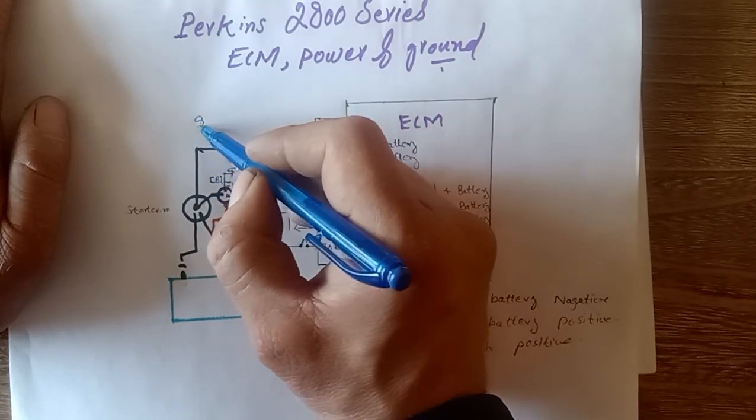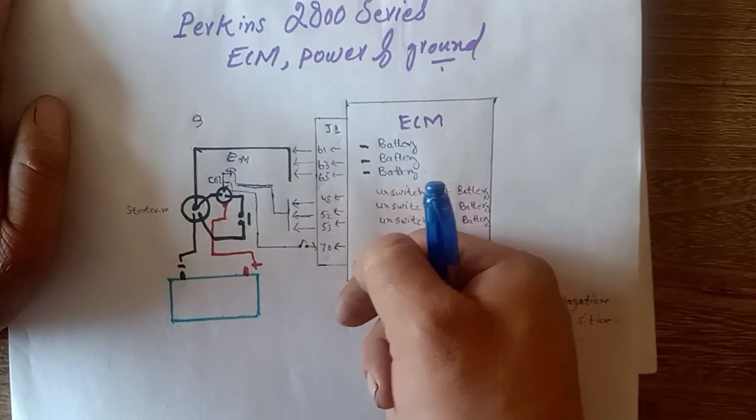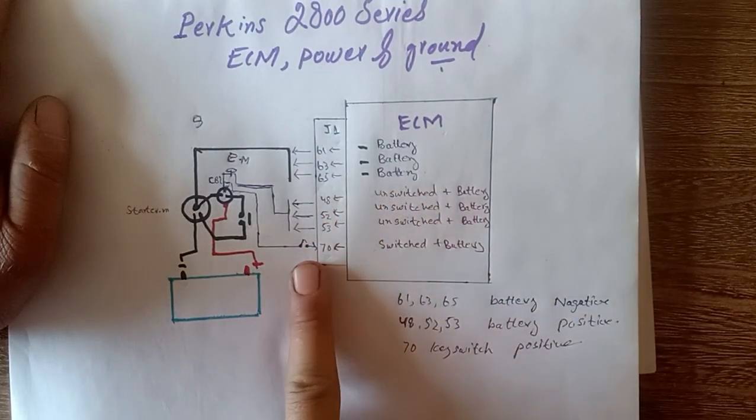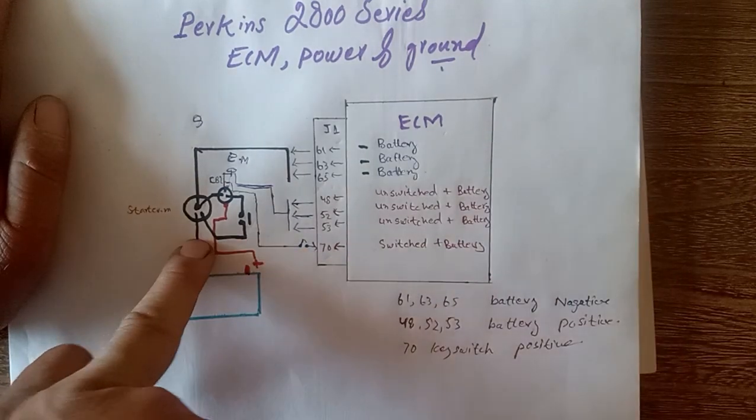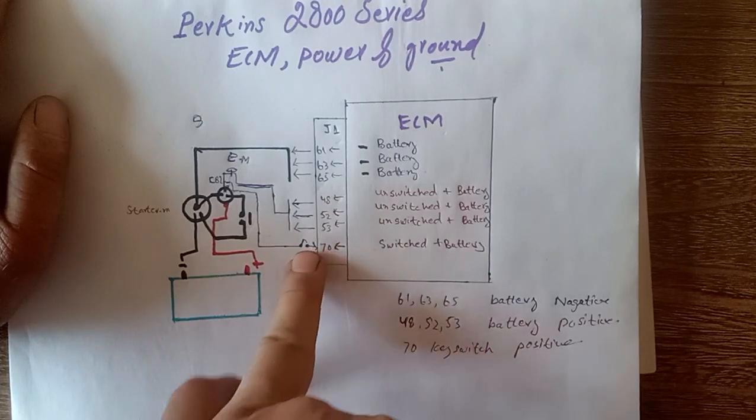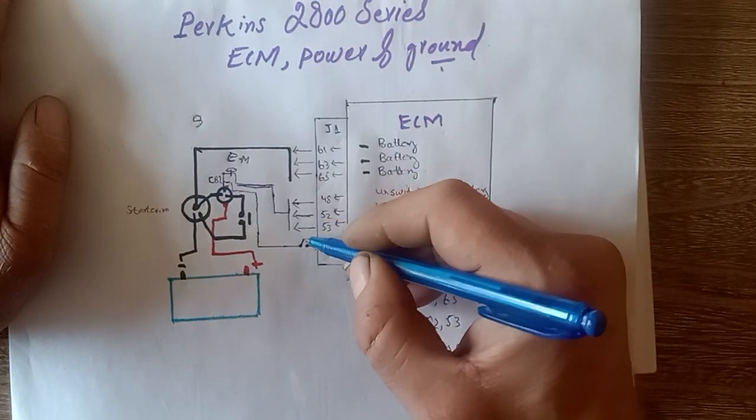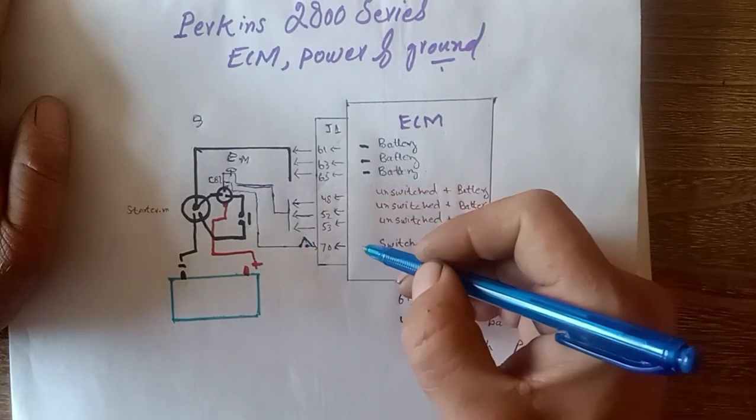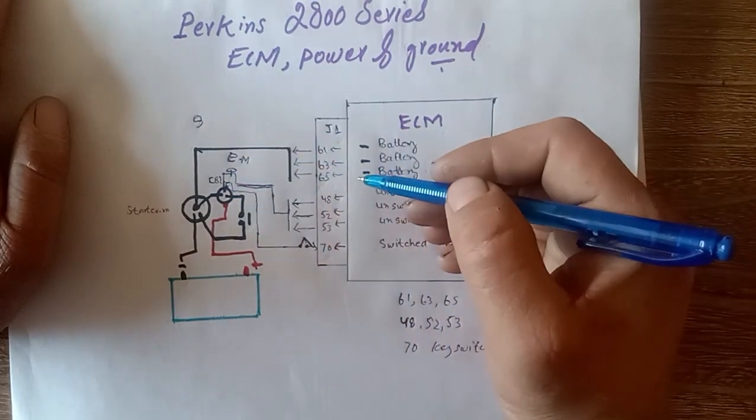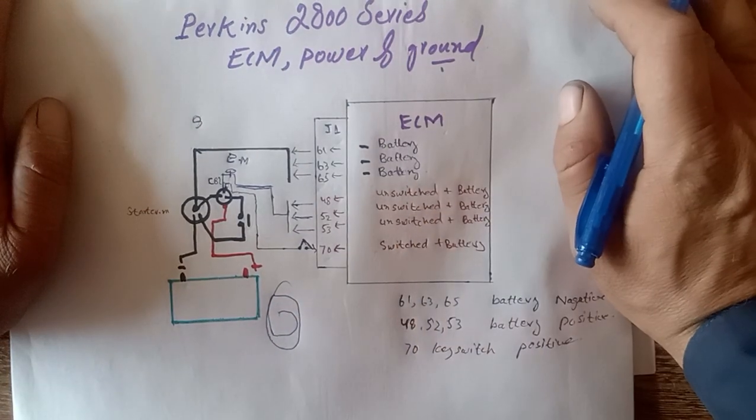And this supply is going to the starter motor small S terminal for signal. When we press the, when we crank the engine or press the key of generator like a control panel button, start button, this switch prior to now in this condition goes closed and this supply goes this way to the starter motor S terminal and engine is turning over. This is the complete ECM energizing supply and starter starting circuit.